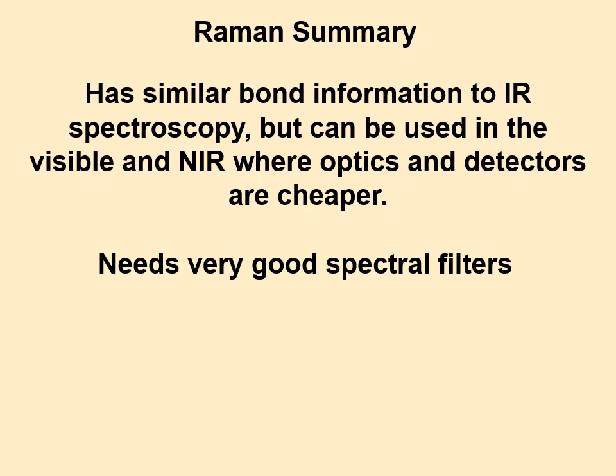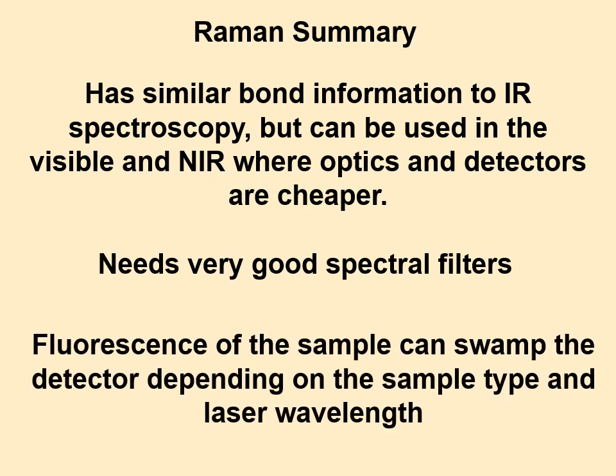You need very good spectral filters because you have to block out a lot of the wrong light just to see the right light. Raman is also often plagued by fluorescence — many molecules fluoresce heavily and create a lot of unwanted light that can swamp your detector. You have to find a way around that, either by changing your laser wavelength or doing some high-speed optical gating.